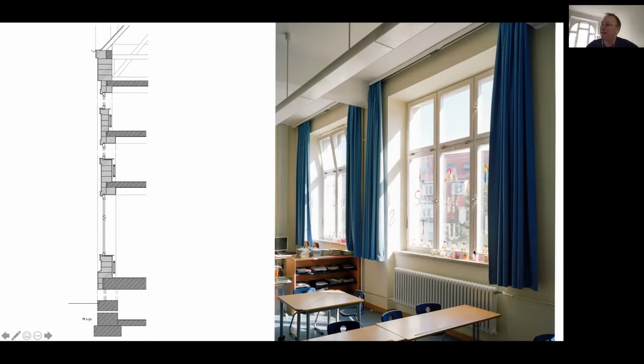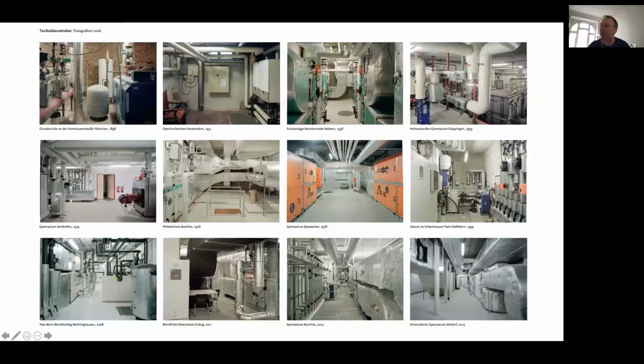Due to the height of these windows, we have these curtains for sun and daylight control, and those curtains are so tall that we get sufficient acoustical absorption. So in terms of air quality, thermal comfort in summer, acoustical comfort, and daylight, this building is the best among all with no mechanical support. Other buildings need mechanical support, which leads to mechanical rooms, compared to the boiler room in this 120-year-old building.